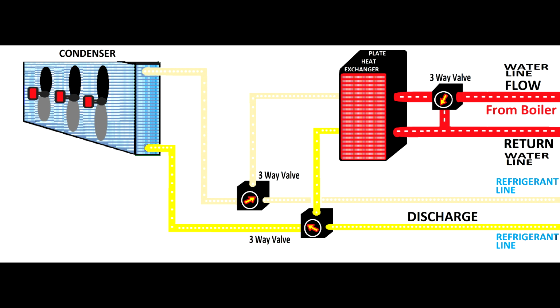So guys, I just want you to understand, this job is more for a refrigeration engineer to take care of this plate heat exchanger. And the refrigeration engineer also has to be trained by a control engineer, and the guy who wrote the control philosophy should advise the software engineer very clearly on what you want to achieve. So this is not just a job where you go and manipulate the valves, because if you do something wrong, you can destroy the refrigeration system. Remember, we just recover the heat from the refrigeration system. We're not creating heat with the refrigeration system.